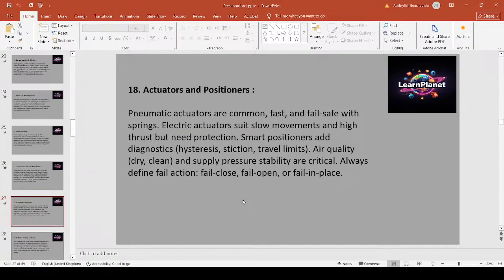Actuators and positioners. Pneumatic actuators are common, fast, and fail-safe with springs. Electric actuators give slow movements and high thrust but need protection. Smart positioners give diagnostics: hysteresis, stiction, travel limits. Air quality, dry and clean, and supply pressure stability are critical. Always define fail action: fail close, fail open, or fail in place.